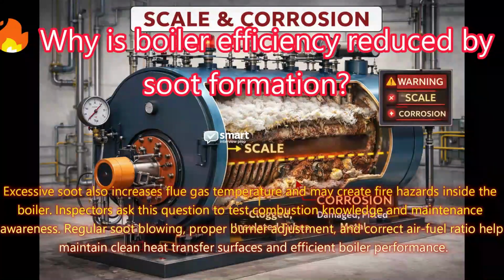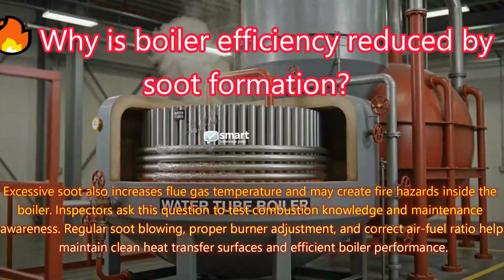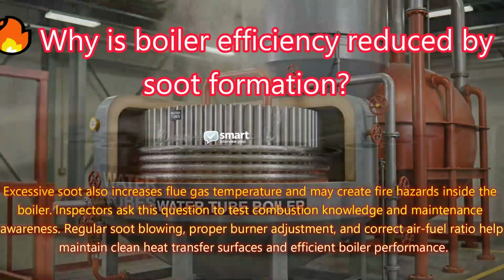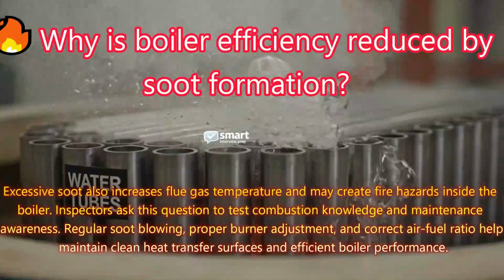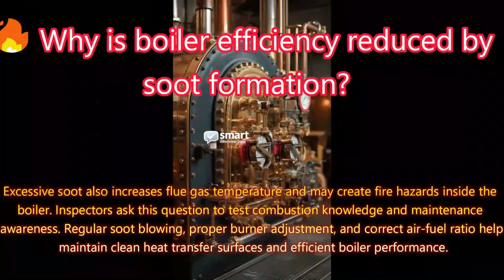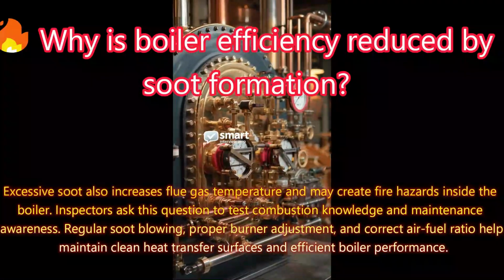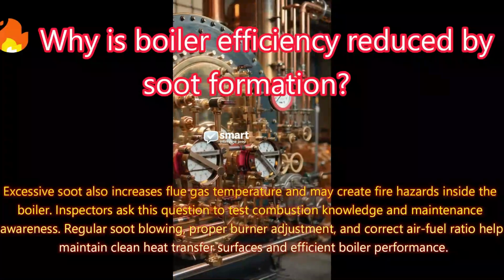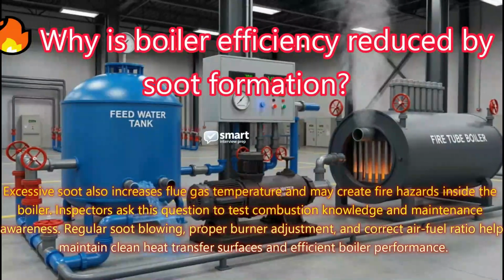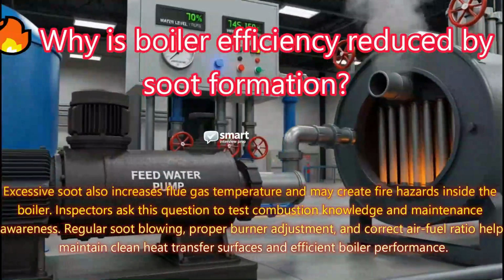Excessive soot also increases flue gas temperature and may create fire hazards inside the boiler. Inspectors ask this question to test combustion knowledge and maintenance awareness. Regular soot blowing, proper burner adjustment, and correct air-fuel ratio help maintain clean heat transfer surfaces and efficient boiler performance.